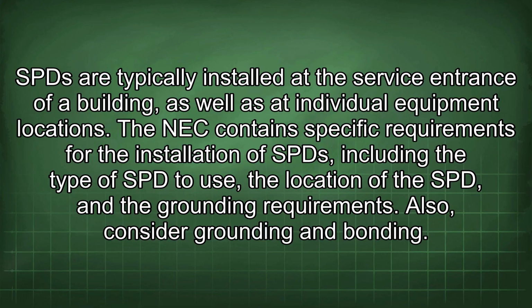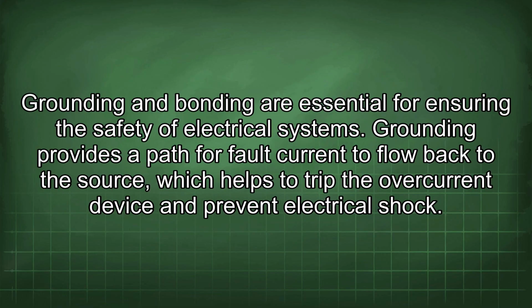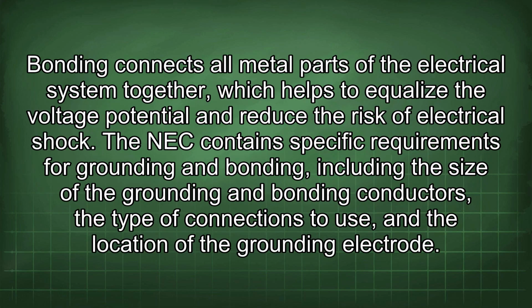Also, consider grounding and bonding. Grounding and bonding are essential for ensuring the safety of electrical systems. Grounding provides a path for fault current to flow back to the source, which helps to trip the overcurrent device and prevent electrical shock. Bonding connects all metal parts of the electrical system together, which helps to equalize the voltage potential and reduce the risk of electrical shock. The NEC contains specific requirements for grounding and bonding, including the size of the grounding and bonding conductors, the type of connections to use, and the location of the grounding electrode.